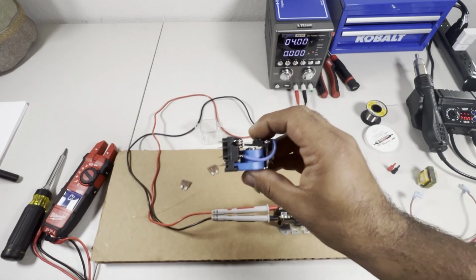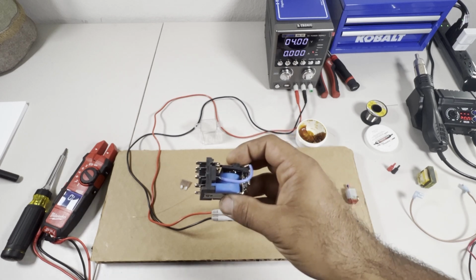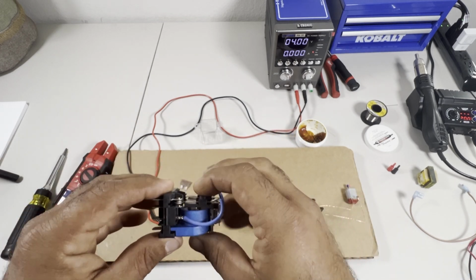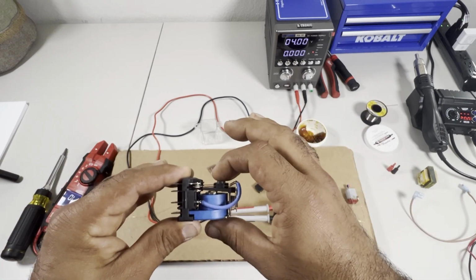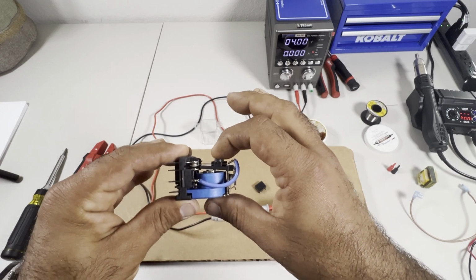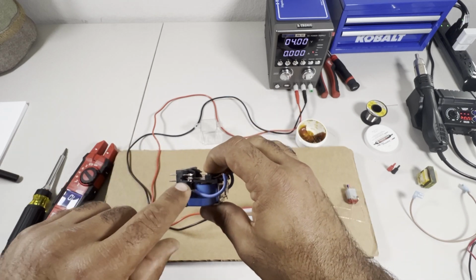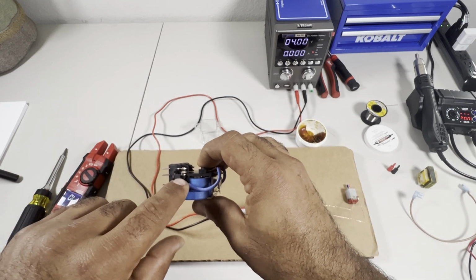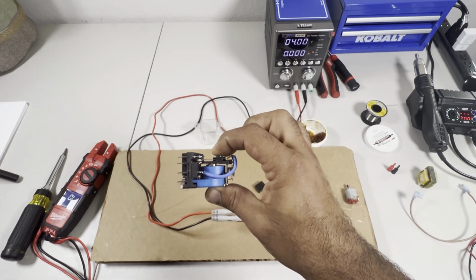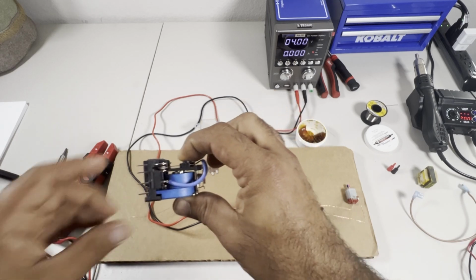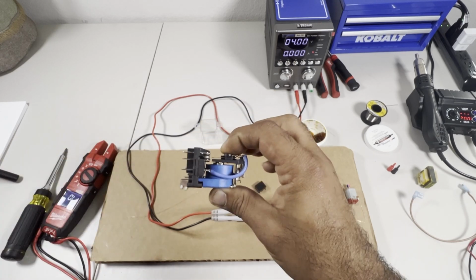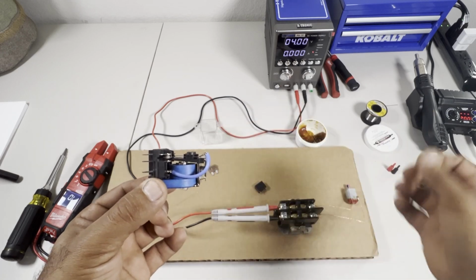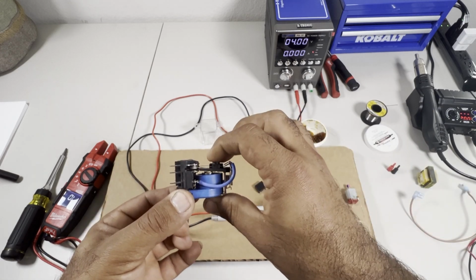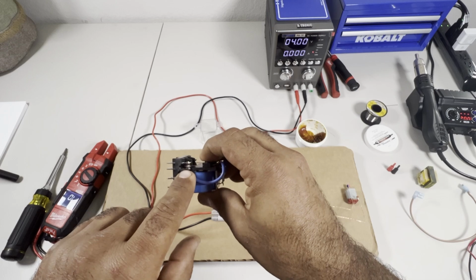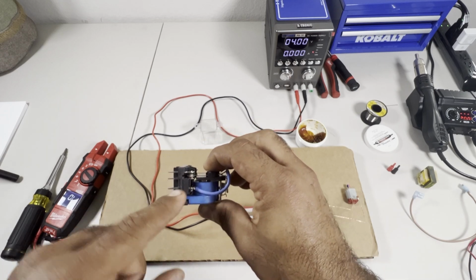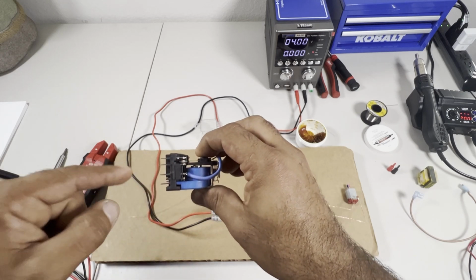And when that happens, those two points of contact are going to start overheating. And at one point, when this contact closes, enough heat is going to be generated between those contacts that they get welded shut. And when that happens, when the power is disconnected from the system and the system should be shutting off, since this one is still closed and welded shut, the power is constantly going through.